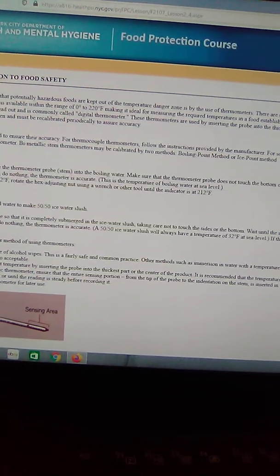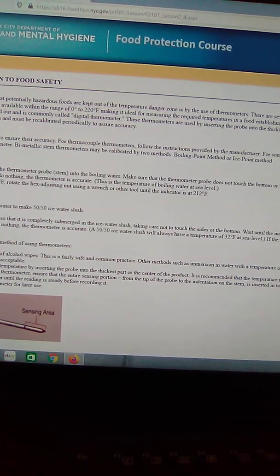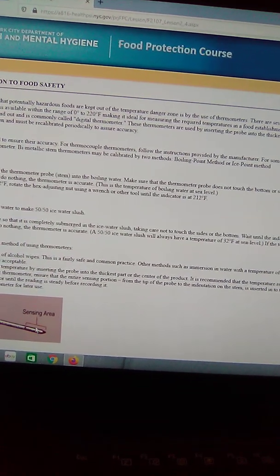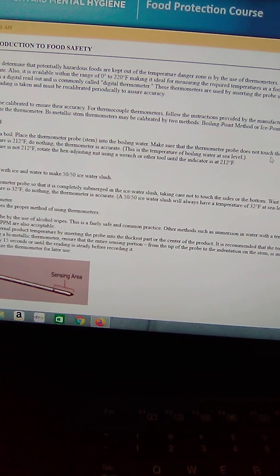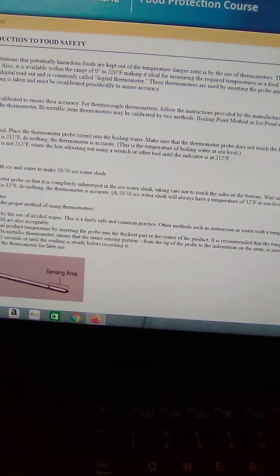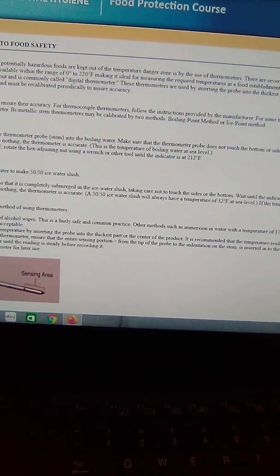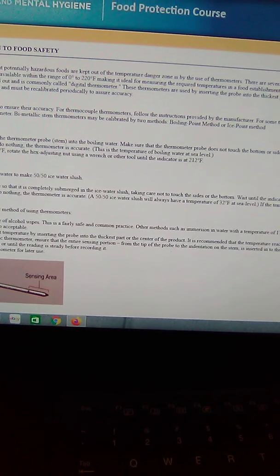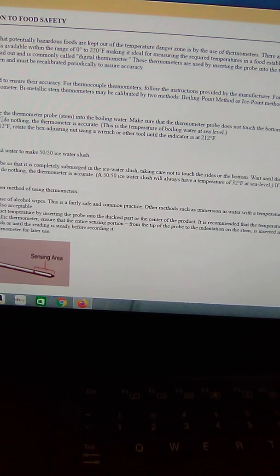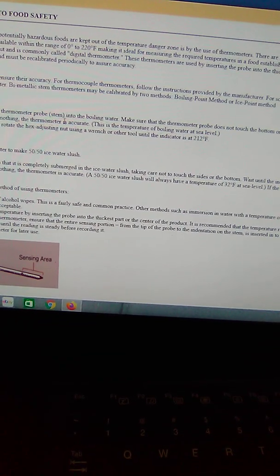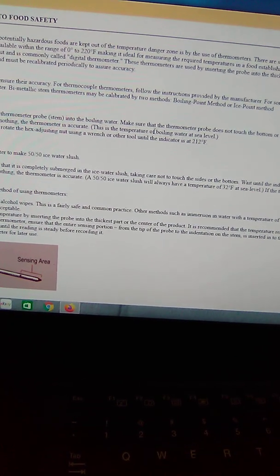Boiling point method. Bring water to a boil. Place the thermometer probe stem into the boiling water. Make sure that the thermometer probe does not touch the bottom or sides of the pan. No contact with the pan now, just in the solution. Wait until the indicator stops moving. Then record the temperature. If the temperature is 212 degrees Fahrenheit, now remember, 212 degrees Fahrenheit, do nothing. The thermometer is accurate. This is the temperature of boiling water at sea level.